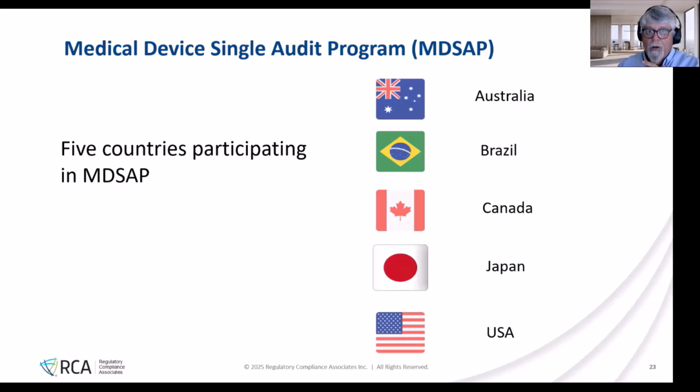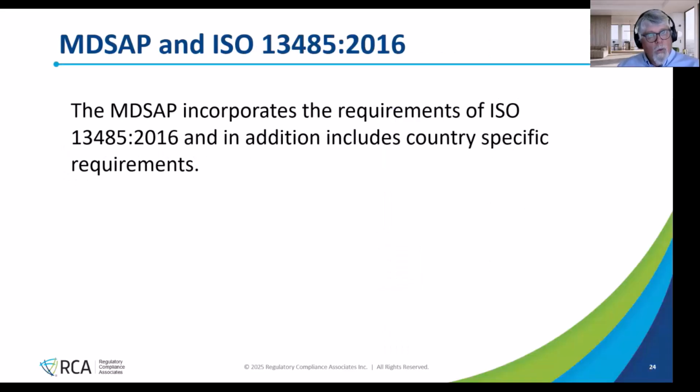So we now have auditing organizations which are commercial, which the organization getting audited has to pay for, and it's part of the MDSAP program. Really cool program. These are the 5 countries that started it. So again, the MDSAP incorporates the requirements of ISO 13485. In addition to, they include country-specific requirements.